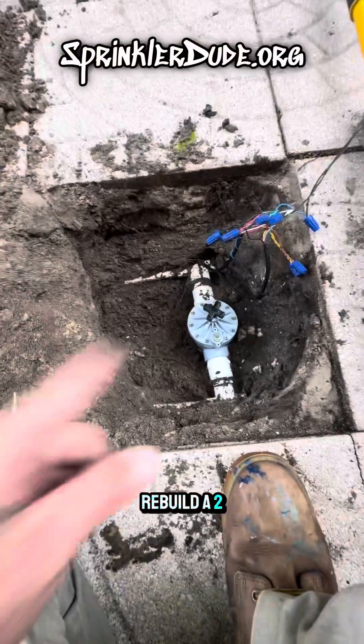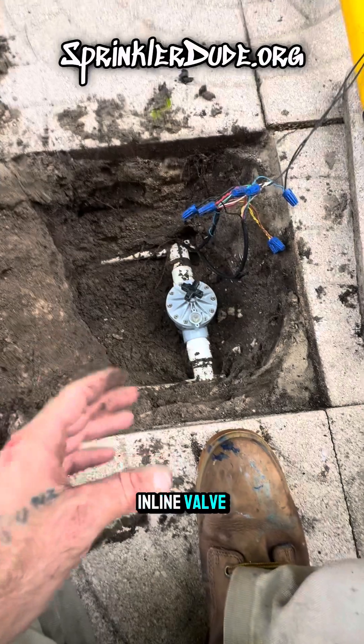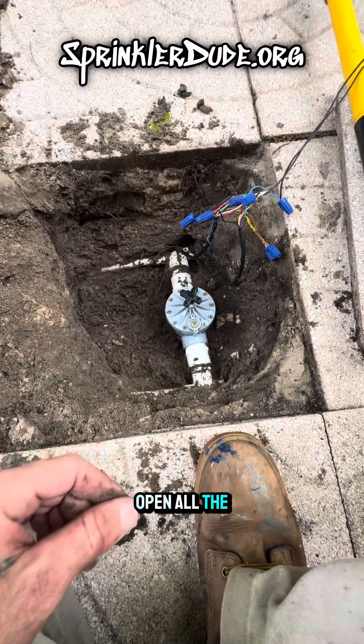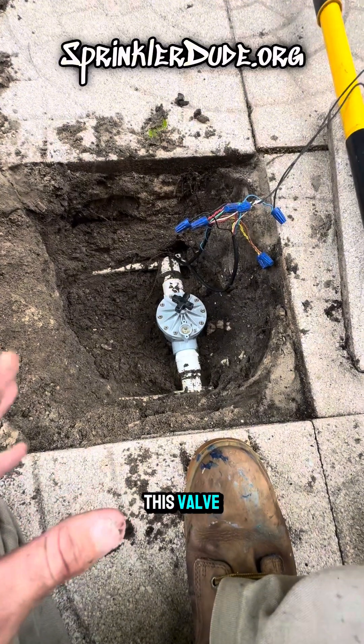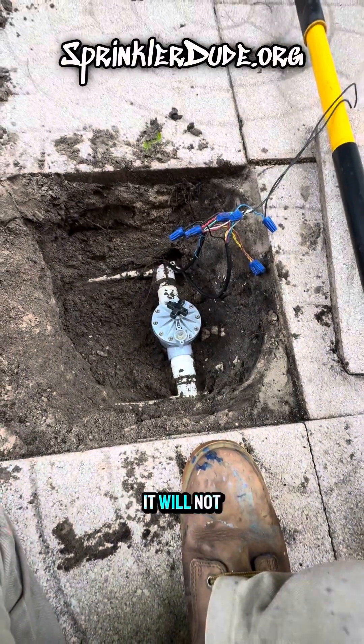Today we're going to rebuild a 216B Irritrol inch-and-a-half inline valve. When we turn on this zone, the valve doesn't open all the way until somebody comes over and starts messing with the solenoid — then it opens all the way. No matter what I do to this valve: clean it out, take it apart, clean all the ports — it doesn't matter. It will not open.